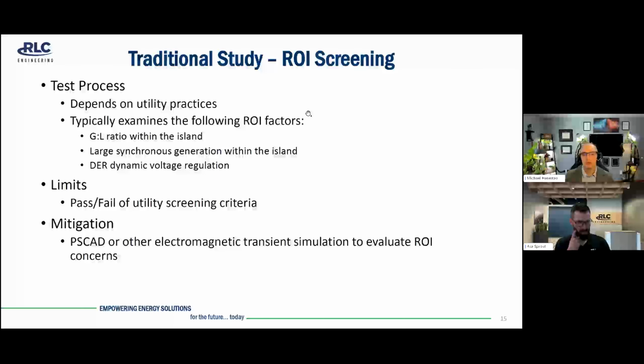Similarly, for a risk of islanding screen, it depends on the utility. Often it's some form of the old Sandia screen, which involves real and reactive power balance checks, looking for large synchronous generators, which might stabilize the frequency within the island, looking for dynamic voltage regulation, such as volt var. And it's a pass or fail based on the screening criteria being used. We usually recommend a PSCAD or other EMT simulation to more accurately evaluate the risk of islanding. If EMT is not being entertained by that utility, it may require DTT as the mitigation. Asa will talk a bit more about that, though.